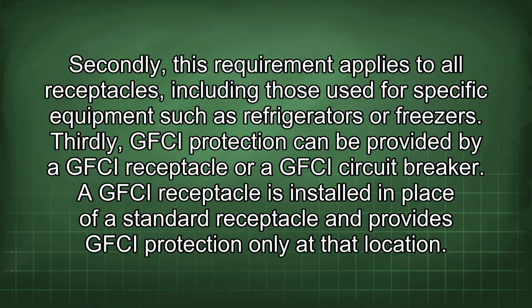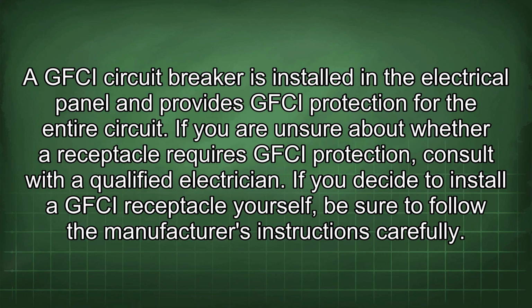A GFCI receptacle is installed in place of a standard receptacle and provides GFCI protection only at that location. A GFCI circuit breaker is installed in the electrical panel and provides GFCI protection for the entire circuit. If you are unsure about whether a receptacle requires GFCI protection, consult with a qualified electrician.